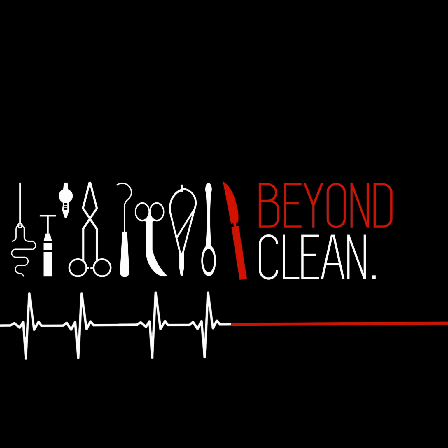So I've seen in real life circumstances where we've failed biocompatibility tests, and maybe we have some inconsistent results where they do retests and they actually show some passing and failing. And when we dig into it, it's because once they use a rinsing tank throughout the day, if they're not changing it enough, then that detergent, and whatever kind of detergent they're using, will build up, and the residual ends up being enough to cause irritation, cytotoxicity. And so that exposure could be there.